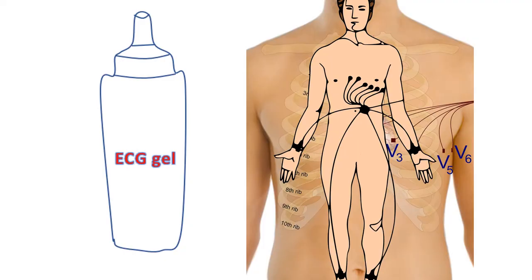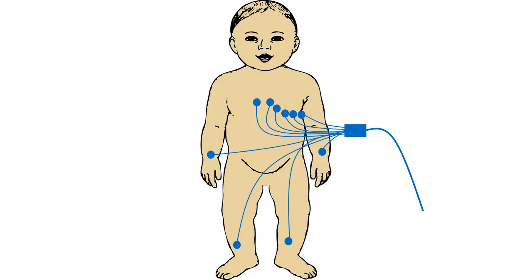To ensure good electrical contact between the recording electrode and the skin, an electrode gel — a good conductor of electricity — will be applied at locations of skin contact. If the designated region is too hairy, it may be necessary to shave the region to get good electrical contact. In young children, small sticky electrodes may be used instead of electrode clips and suction electrodes for the chest.